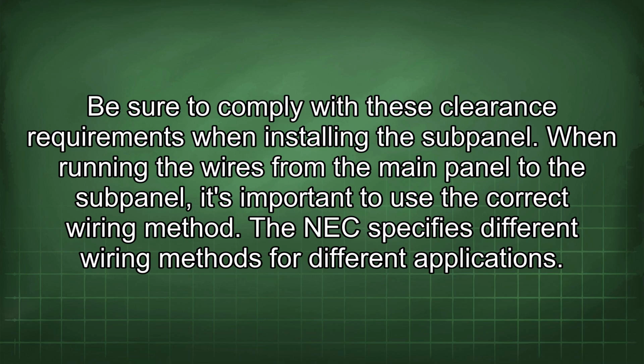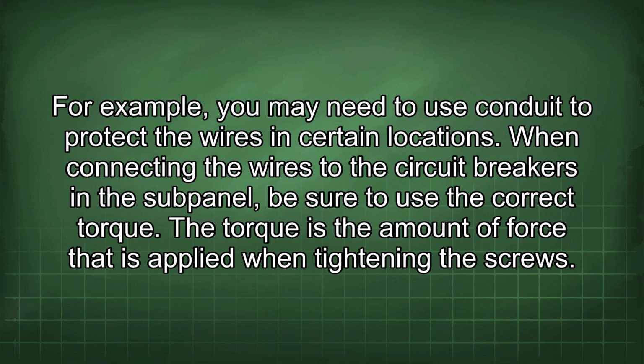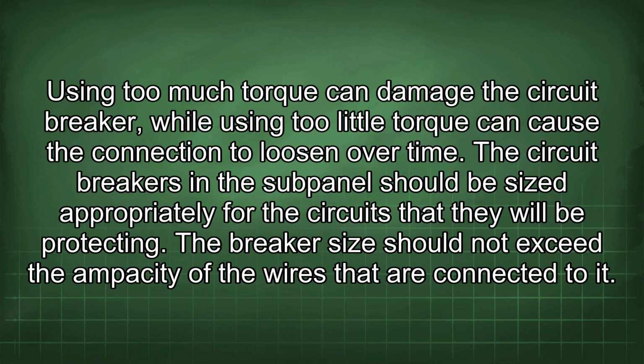When running the wires from the main panel to the subpanel, it's important to use the correct wiring method. The NEC specifies different wiring methods for different applications. For example, you may need to use conduit to protect the wires in certain locations. When connecting the wires to the circuit breakers in the subpanel, be sure to use the correct torque. The torque is the amount of force that is applied when tightening the screws. Using too much torque can damage the circuit breaker, while using too little torque can cause the connection to loosen over time. The circuit breakers in the subpanel should be sized appropriately for the circuits that they will be protecting. The breaker size should not exceed the ampacity of the wires that are connected to it.